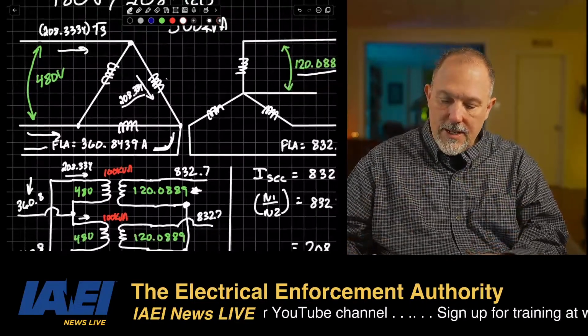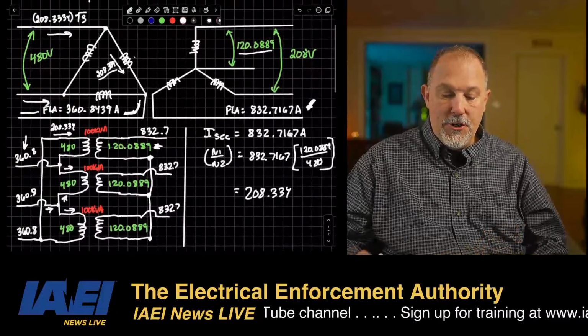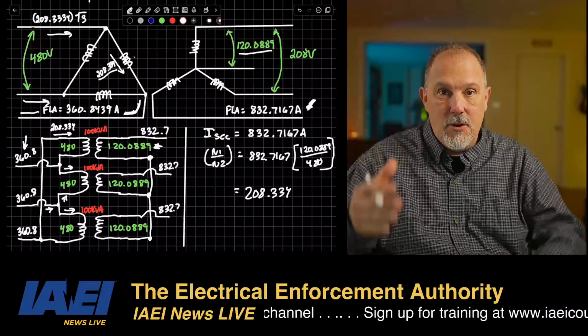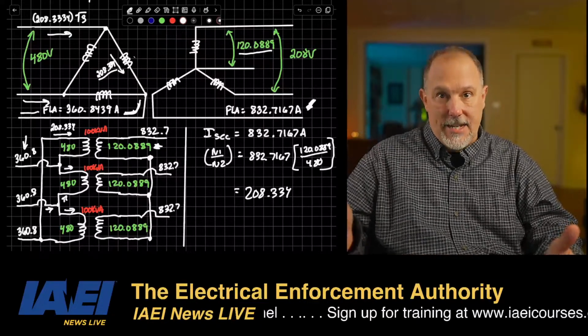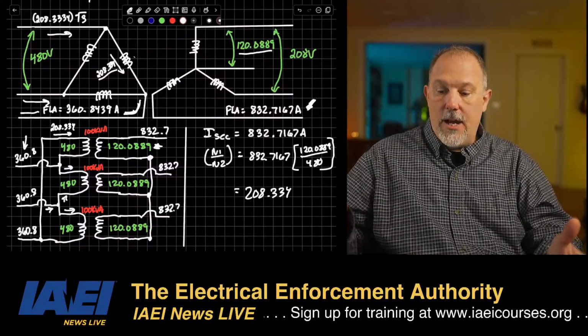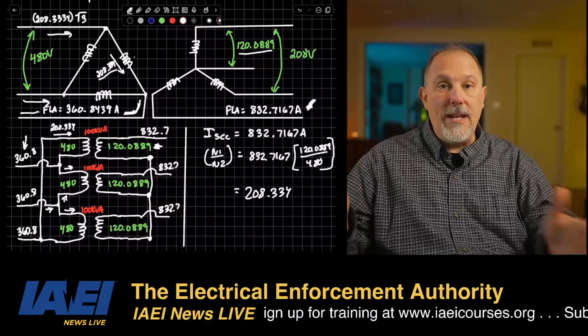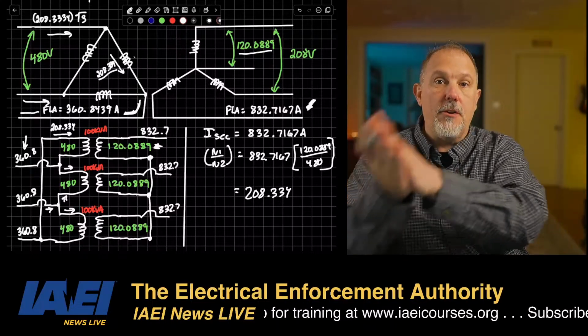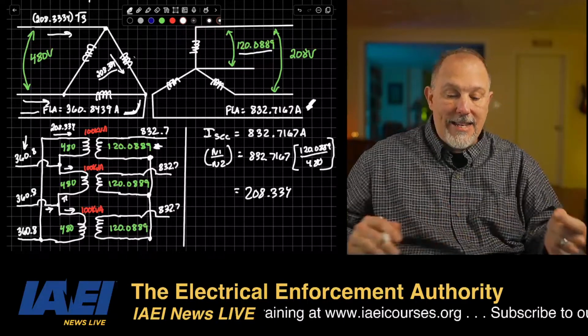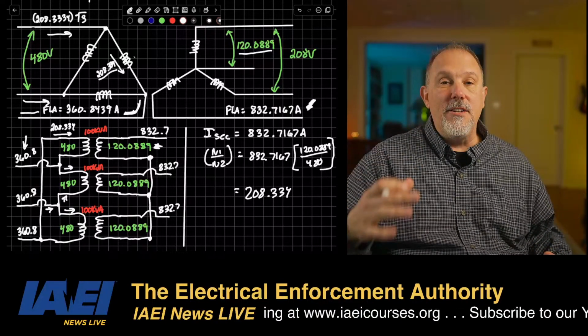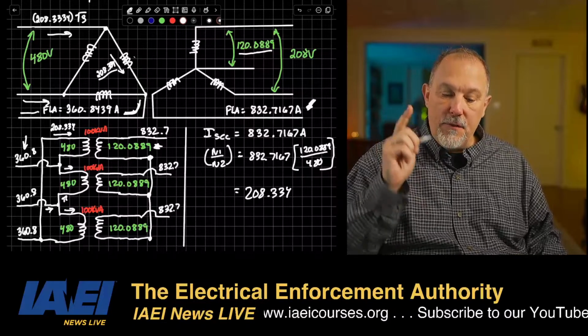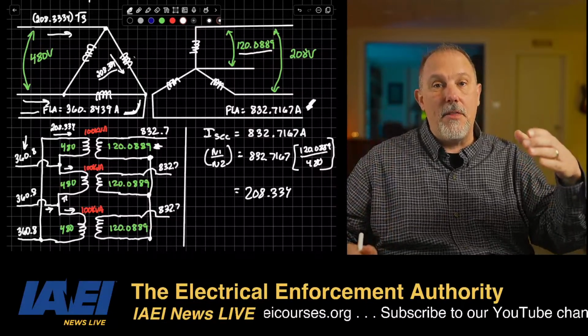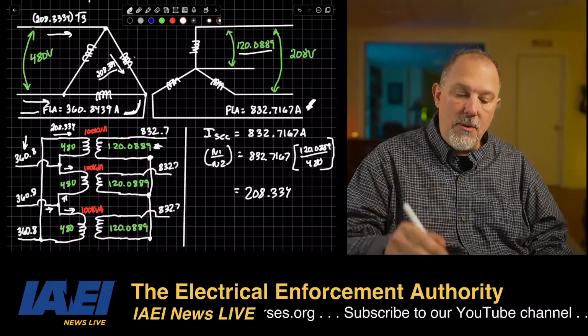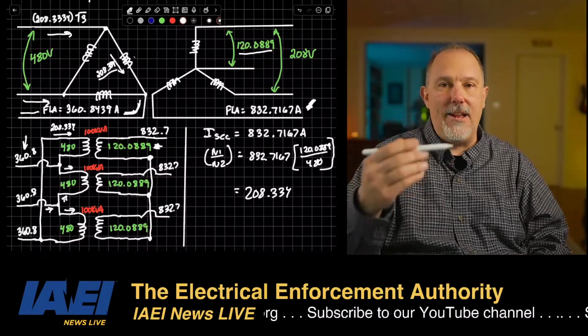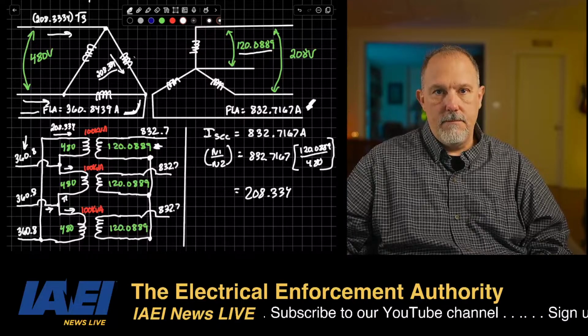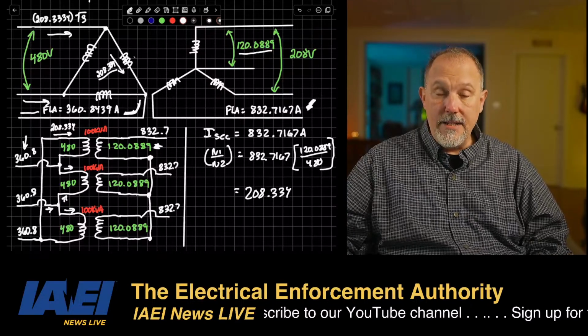So I can do my phase-to-phase voltage on the primary, phase-to-phase voltage on the secondary. I can use my 480 to 208 to reflect my secondary currents to my primary. I can use 480 to 120, but I've got to remember, if I do 480 to 120 and I have a delta on the primary, I'm only calculating what's in the delta. I have to add on the square root of 3. Make sense?